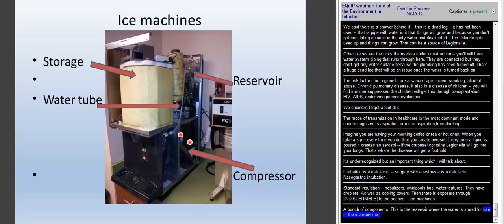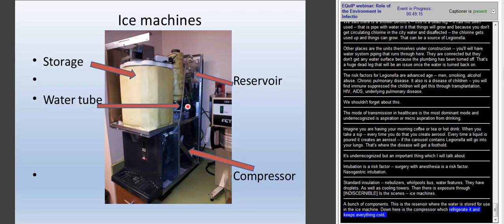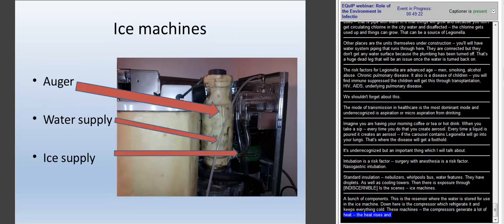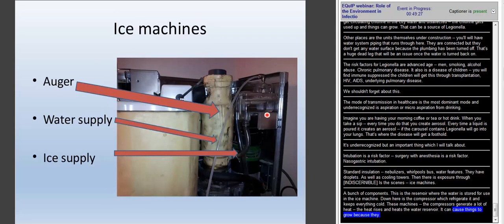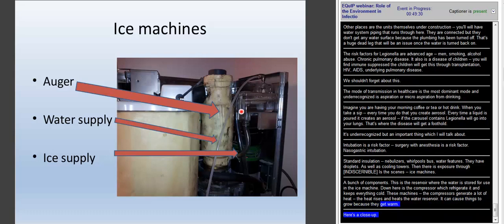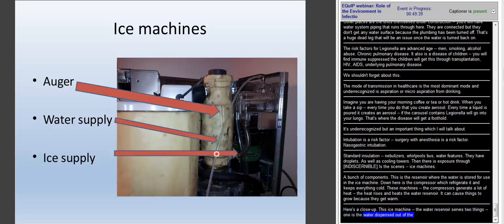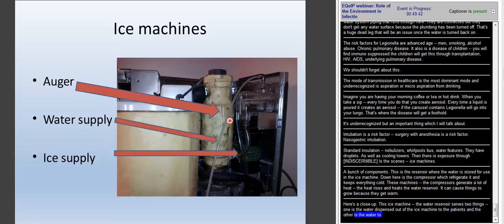But these compressors generate a lot of heat. The heat rises and it heats the water reservoir, and can cause things to grow and amplify because they get warmer. Here's a close-up of it. This water reservoir serves two things: one is the water dispensed out of the ice machine by glass to patients. The other is a water tube that comes down and hits the actual ice machine and auger, which creates a tube of ice that flows down into the big storage bin.